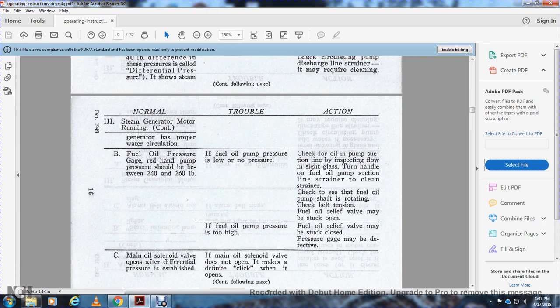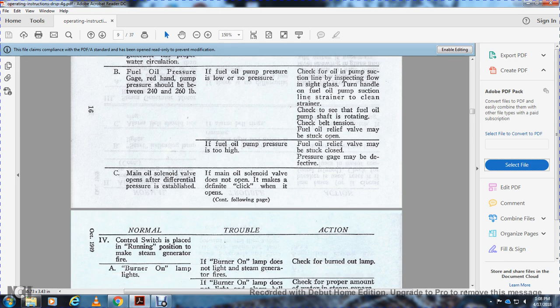Alright, if the fuel oil pump pressure is too high, the action is to check that the fuel oil relief valve may be stuck closed, or the pressure gauge may be defective. C, the main oil solenoid valve opens after differential pressure is established. If the main oil solenoid does not open, note that it makes a definite click when it opens.